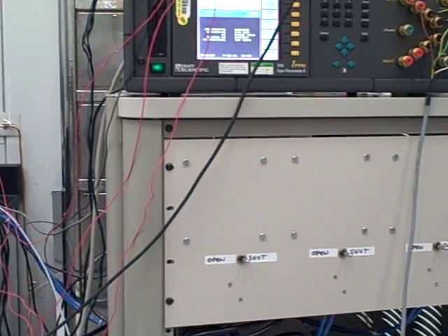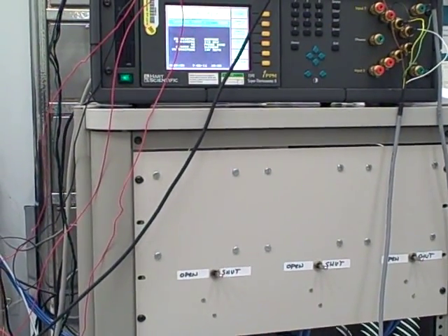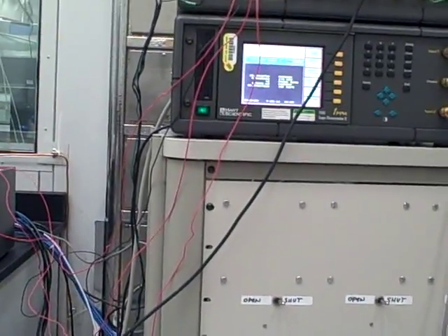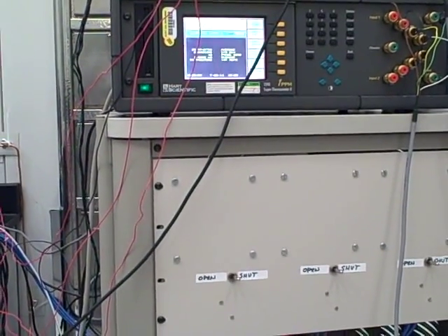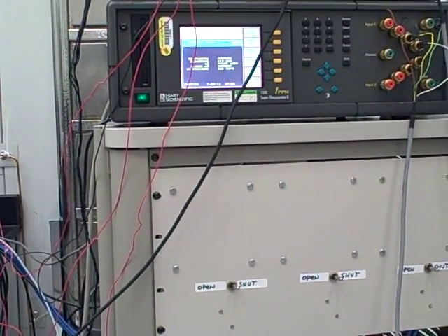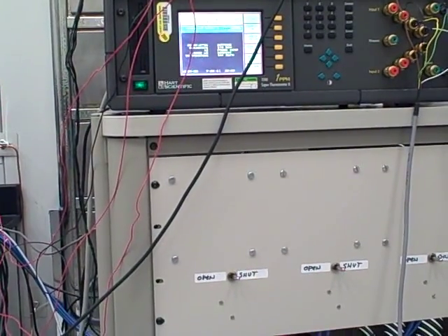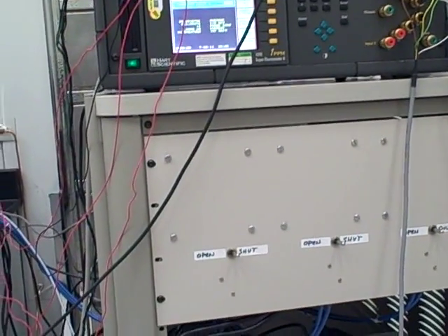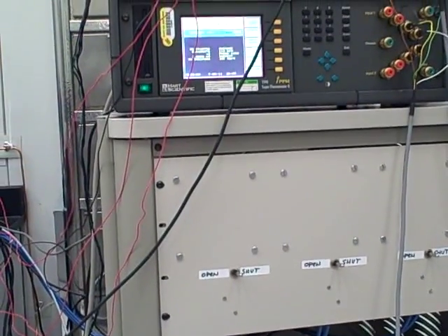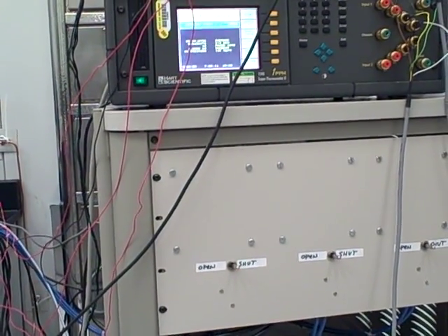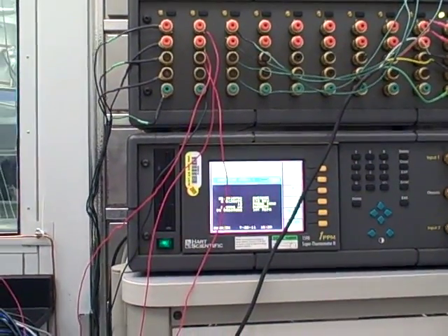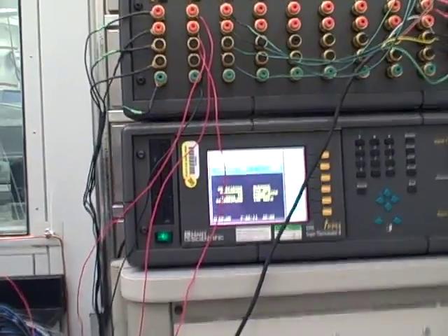And how often do you have to calibrate them? About every 2 years or so. That's not bad. But we need repeatability of thermometers to about 20 milli-C, so 0.02 C. That's good enough for what we do here. If I needed better accuracy than that, I'd probably have to calibrate more often, because these things do drift a little bit with use, and if you bang them a little bit, they'll change.